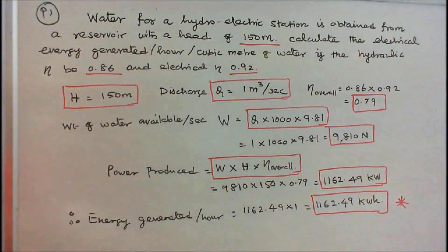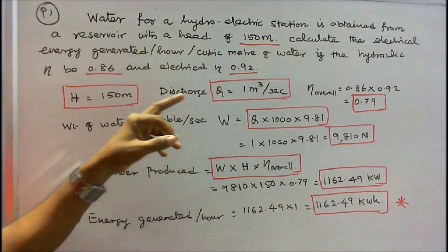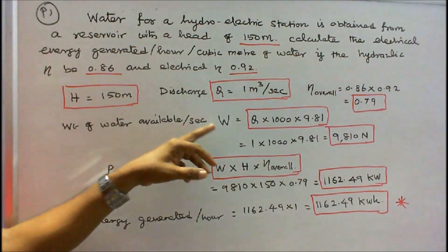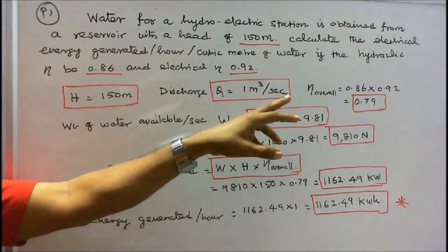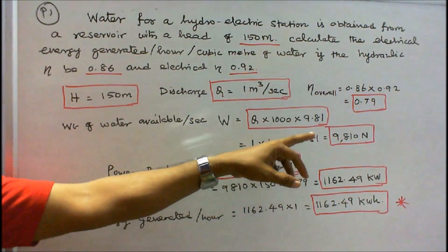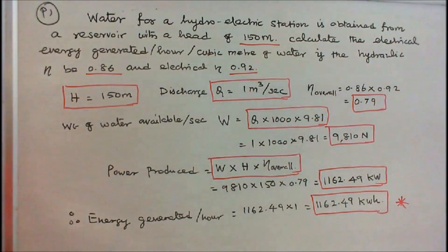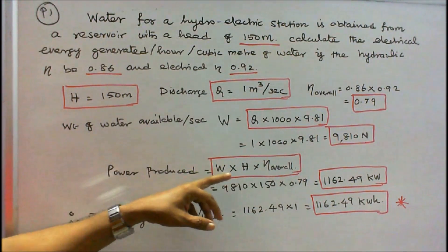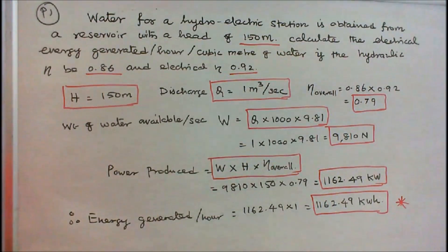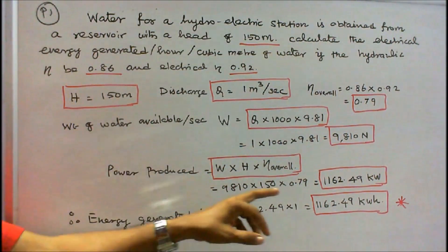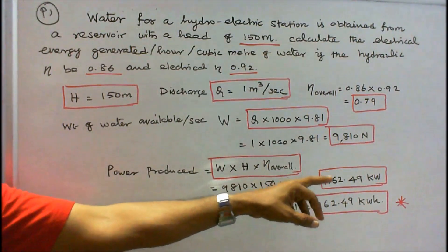H is given as 150 meters. Discharge Q is given as 1 cubic meter per second. Weight of water available per second: W = Q × 1000 × 9.81 Newtons. So W = 1 × 1000 × 9.81 = 9810 Newtons. Power produced = W × H × overall efficiency = 9810 × 150 × 0.79 = 1162.49 kilowatts.